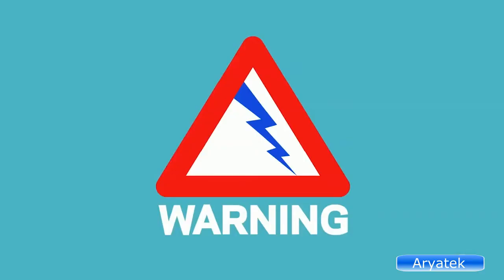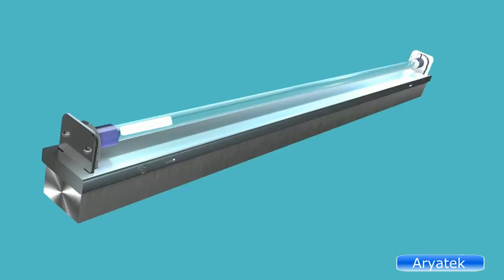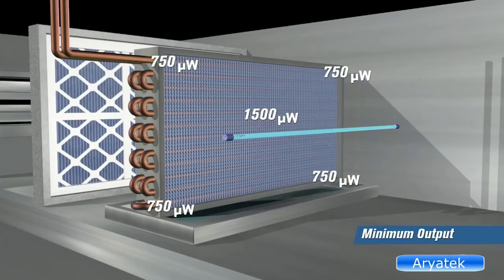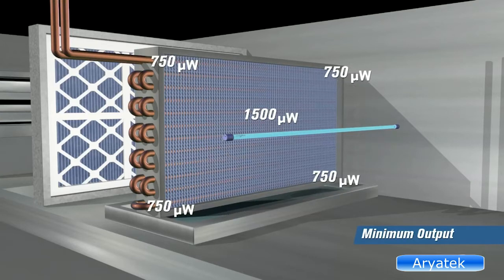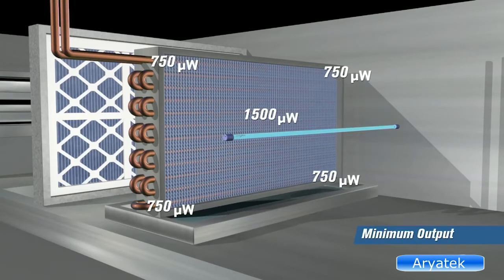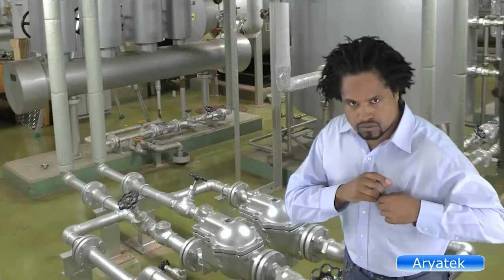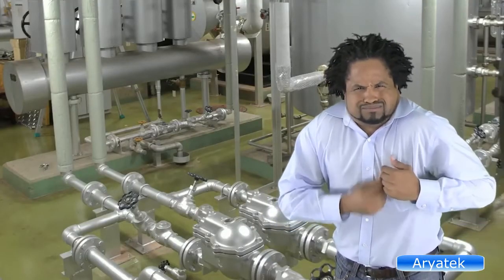A caution is necessary. Not all UVC is created equal. The output of UVC is invisible microwatts and is not always proportional to the watts coming from the electrical supply. In order to have sufficient microwatts to kill both the mold growing in the coil and the microbes in the air, SterilAir recommends at least 750 UVC microwatts at any point on the coil face. Without maintaining these standards, the people in the building will remain vulnerable.